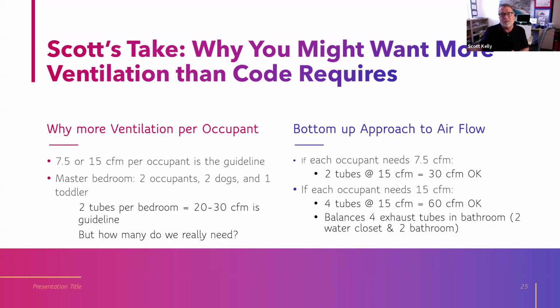So the bathroom is actually going to need 2 tubes, because by code, if we're not going to have the exhaust fan in the bathroom, then we're going to have continuous airflow of exhaust from the bathroom through the balanced ventilation system, that's the ERV, at 20 CFM minimum 24/7. Yep. So those 2 tubes in the bathroom are going to provide that for the code, but the bathroom contains a water closet also. So now you have to treat that the same way. So the water closet needs 2 tubes.